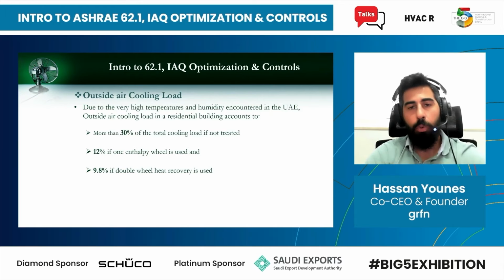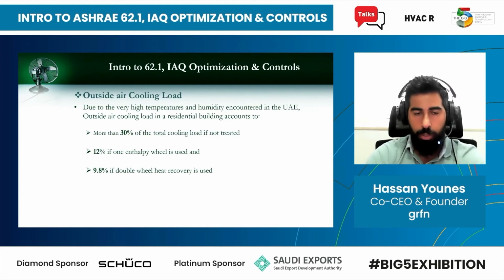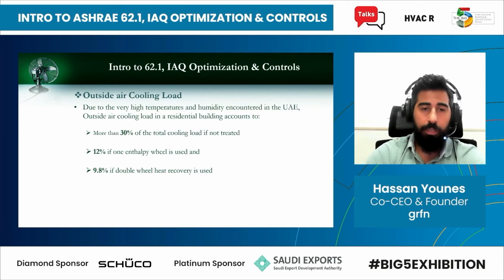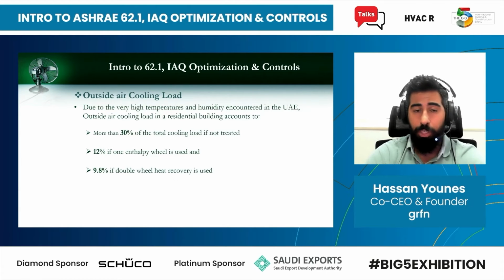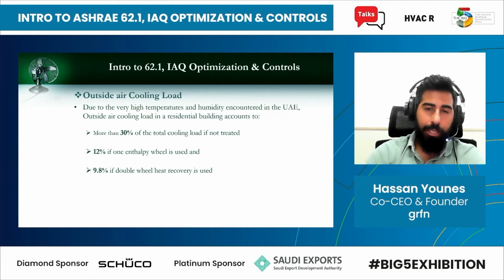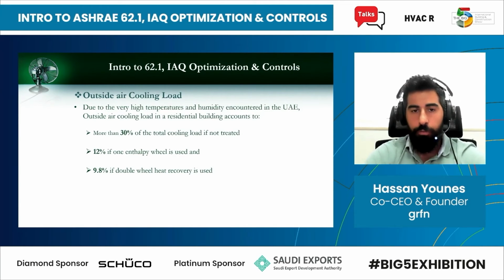In terms of energy recovery, we always recommend using energy recovery because it does reduce the cooling load drastically. You might reduce 60% to 70% of the cooling load if you use heat recovery with a single wheel. Maybe reduce 60%. With a double wheel, you might reduce 70% of the cooling load on the outdoor air handling unit. And it will reduce your chiller capacity or district cooling connected load. It will reduce the amount of pumping required. So it has a cascading effect. It might add a little bit of cost on the heat recovery device itself, on the outside air handling unit, but it will reduce the cost of cooling capacity and the associated auxiliaries.